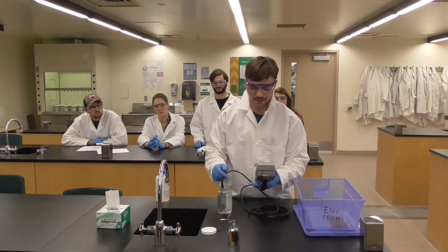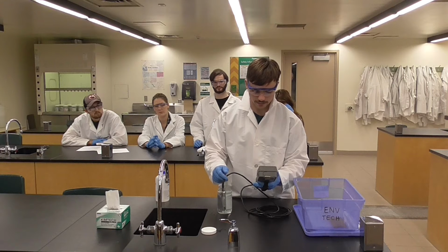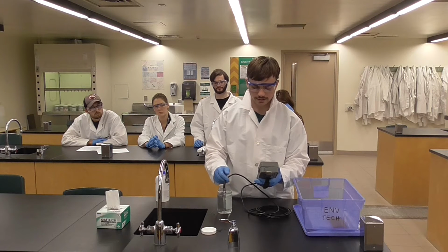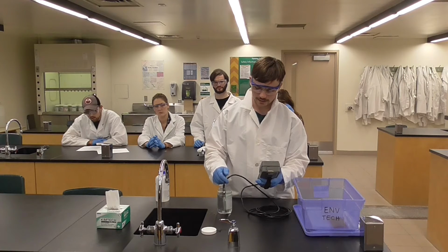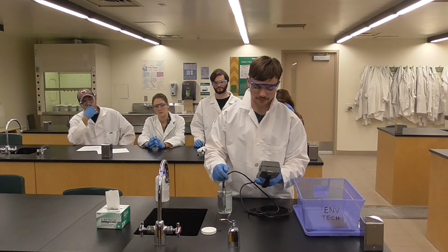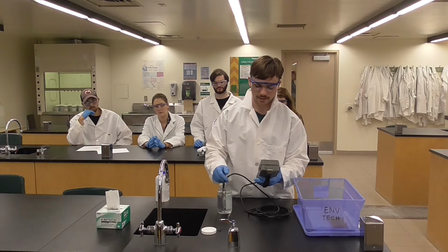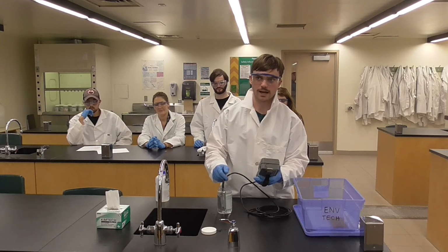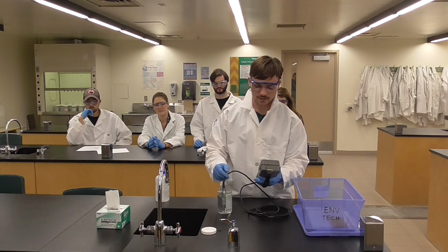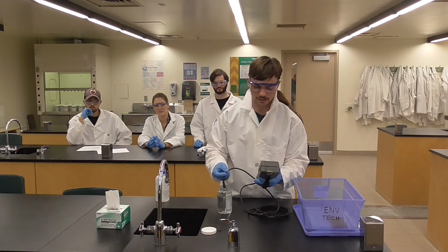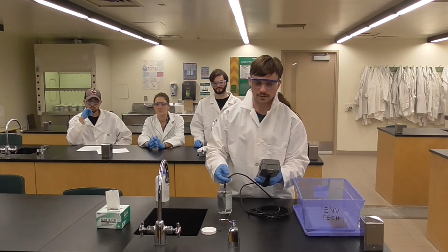The specific conductance for this water sample is 490.6 microsiemens per centimeter, and that'll be a reading which is extrapolated based off what the water temperature would be at 25 degrees Celsius. Right now the current water temperature is 22.0 degrees Celsius.